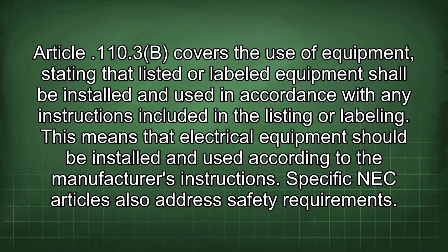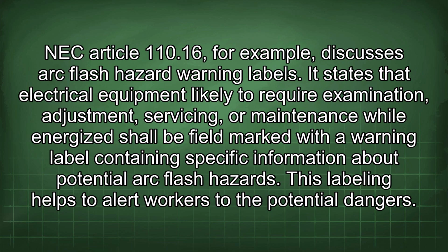Specific NEC articles also address safety requirements. NEC Article 110.16, for example, discusses arc flash hazard warning labels. It states that electrical equipment likely to require examination, adjustment, servicing, or maintenance while energized shall be field marked with a warning label containing specific information about potential arc flash hazards. This labeling helps to alert workers to the potential dangers.